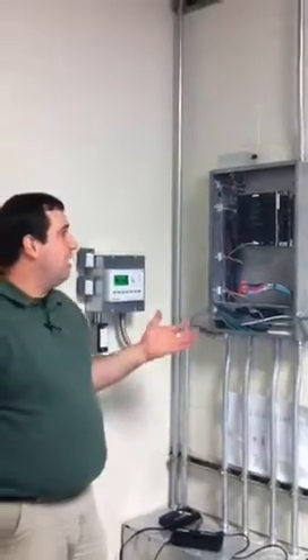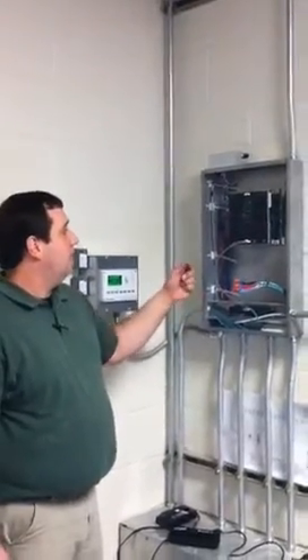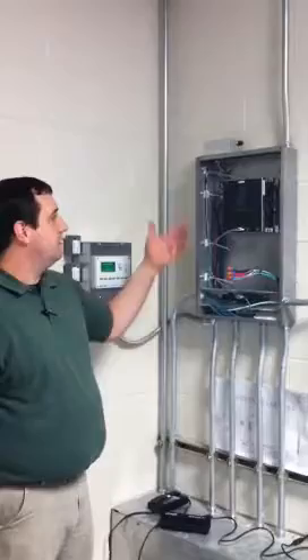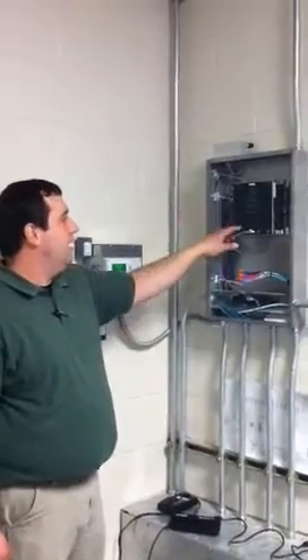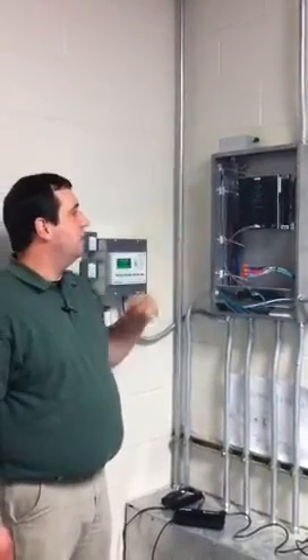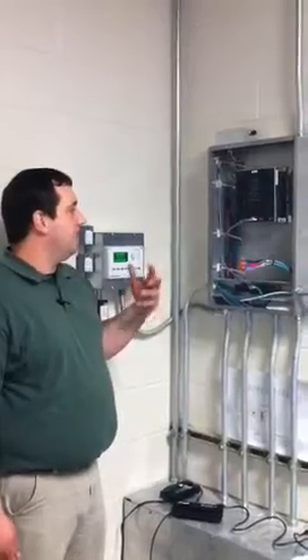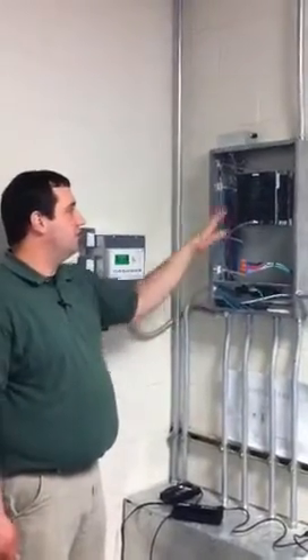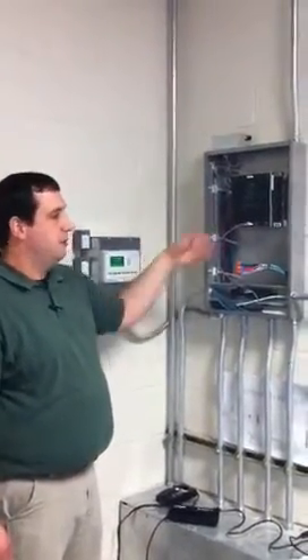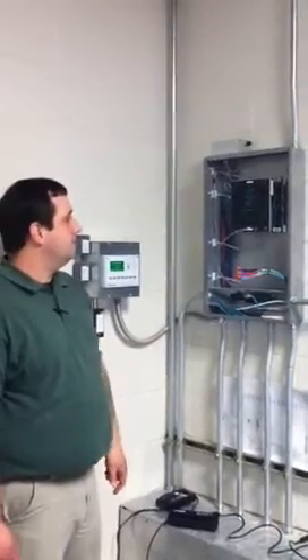In the event that the module should fail, it can be field replaced. You pull out the module, pop the new one in, and the ID is set in the window itself. And that's basically all there is to change in it. There's no other programming. Once the ID is set, the program will recognize it and pick it up where it was.